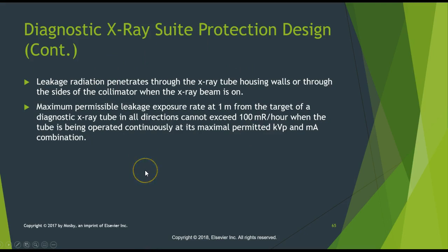Leakage radiation penetrates through the X-ray tube housing walls or through the sides of the collimator when the beam is on. Maximum permissible leakage, at a distance of 1 meter from the target of the X-ray tube in all directions, cannot exceed 100 milliroentgens per hour. And that's if the tube is being operated continuously at the maximum kVp and mA.